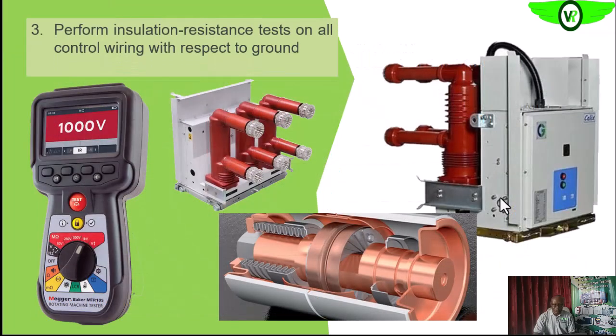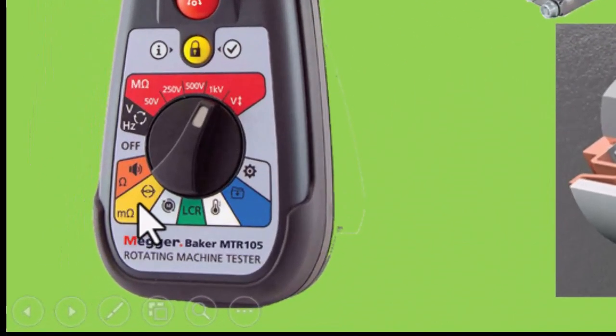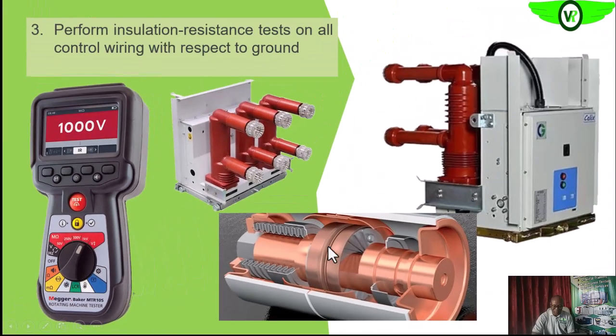Like we said before, you perform insulation resistance on the control wiring. But in this case again, you need to be very careful. Follow the procedure recommended by your manufacturer so that you will not destroy sensitive electronic components in the control circuitry. This is a very versatile meter that we can use also. This is the low resistance section of the meter. You just turn this selector switch, and then you probe both ends when it is closed, especially when you are looking at contact resistance.